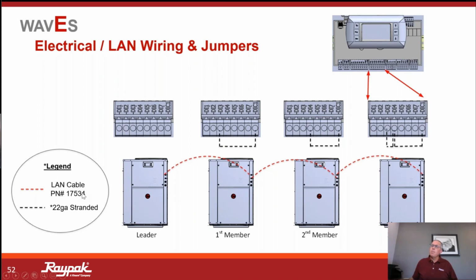Here's the reference of the part number. And we recommend 22 gauge stranded as your jumper. Those would have to be placed. They do not come as standard. Any questions with wiring units in cascade? It's pretty straightforward, pretty easy to navigate. Simple daisy chain wiring. Paul, is there a minimum stranding requirement for the 22 gauge, or does it matter?